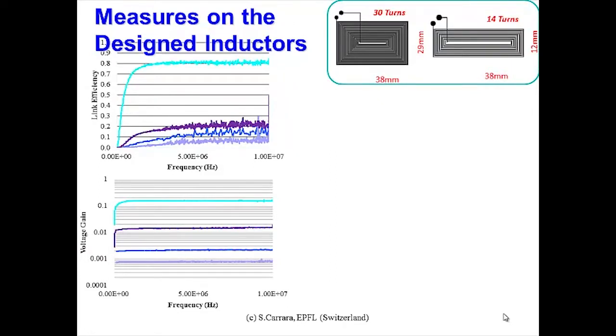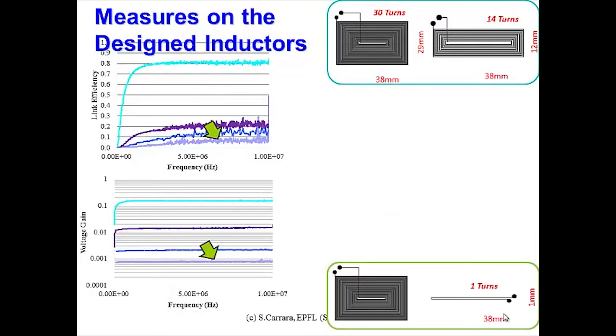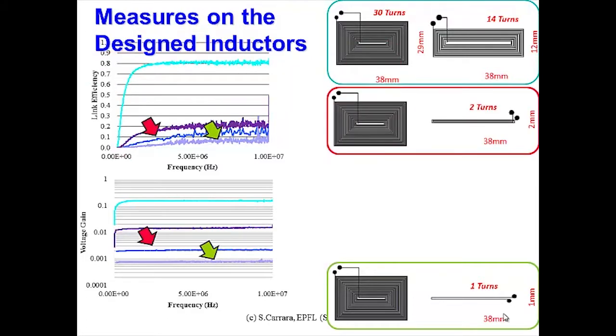The problem is that in all the published papers, they have reasonable sizes also for the receiving coils. What we immediately observed is that if we go down with the lateral size of our receiving coil, our link efficiency and voltage gain drop to unbelievable low values. So the only chance to increase the link efficiency as well as the voltage gain is to increase the number of turns, but this causes us to lose the tiny lateral size of our device.